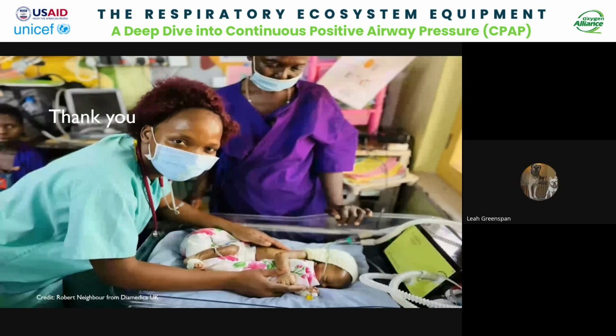Thank you for this excellent question. There have been many studies over time that look at disability and death. We used to maintain saturations around 88 to 93%, but we saw that there was an increase in death and disability. So now the ideal saturation is somewhere between 90 and 95%. That's what you're looking at your pulse oximeter to read, your oxygen saturation at the patient level. How you get to that point is where you dial your different flows, whether it's medical air and oxygen, or however you use your device, you want your blended oxygen to maintain the saturation at 90 to 95%.